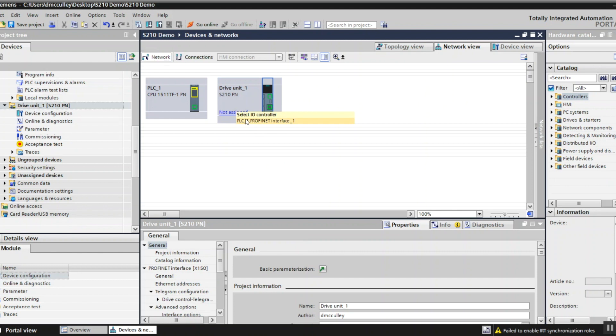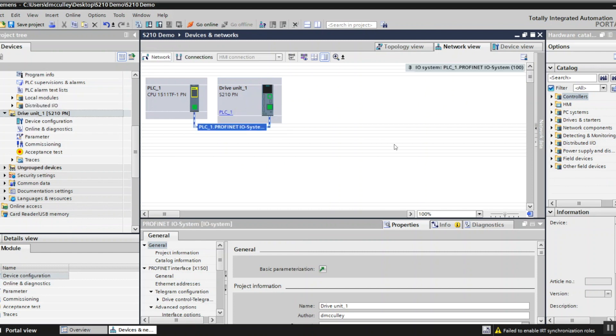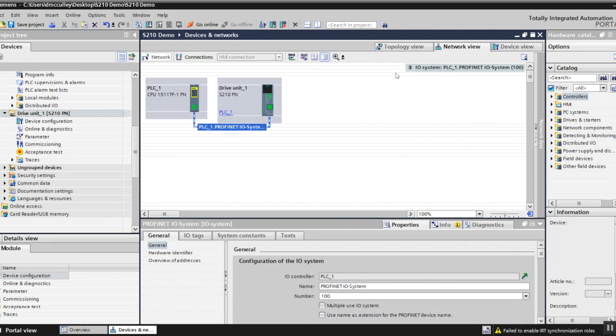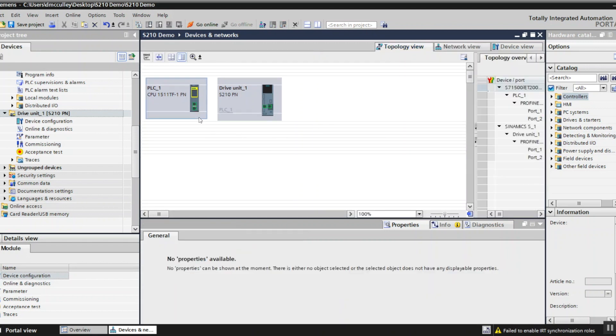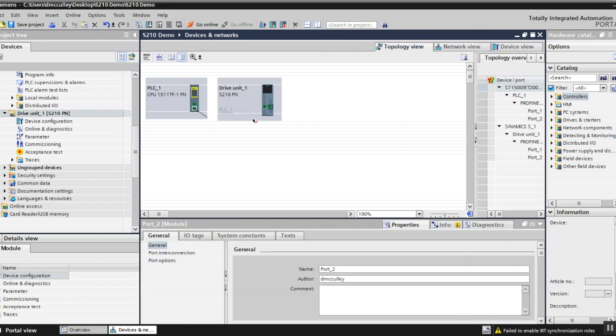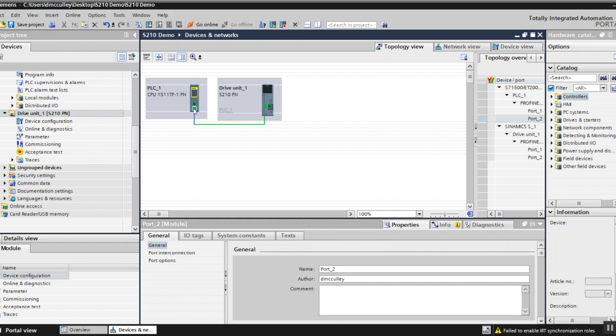Then assign my drive to my PLC network. I'm going to topology view and connect the topology exactly how it's wired physically. So I go from X1 P2 on my PLC to X150 P1 on my drive.